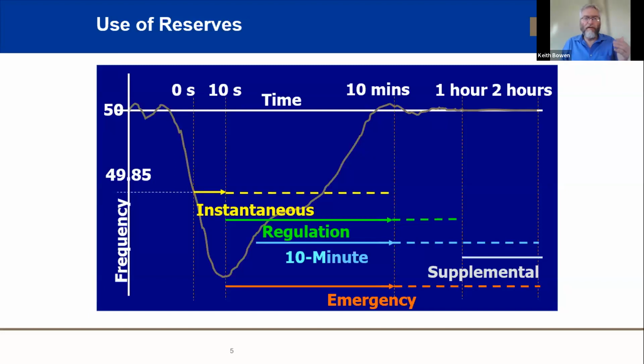One of the most important things for that 10-minute window is to make sure you're able to restore the regulating and instantaneous reserves, in case there's a second event, or even, at worst, a third event, because you're always trying to restore the reserves.